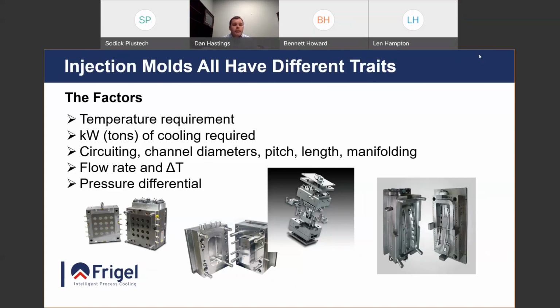Circuiting channels: diameter, pitch, length, manifold. These are all things to consider. The bigger is probably the better, so we can get more flow through them. As you could probably tell, I really do not like quick connects. If you have a 1/2 inch quick connect, really you have a 3/8 inch connection point, because the quick connect has that orifice that restricts flow. So if you're thinking you're doing good with a 1/2 inch quick connect, you really have half of that.